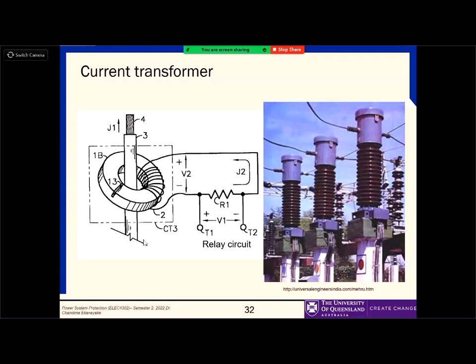When you have magnetic circuits, what is the assumption now? Let's say the current in the primary conductor is proportional to the current in the secondary side. There's an assumption for that. Why can we write that? How do you transfer that signal from primary side to secondary? This will create a flux, and that flux will create this current. So my assumption is that this current is proportional to the rate of change of flux here, and the production of that flux is proportional to this one.